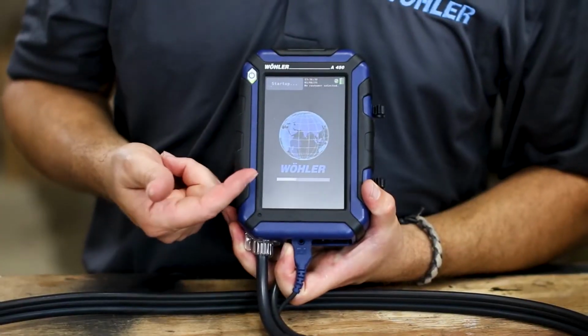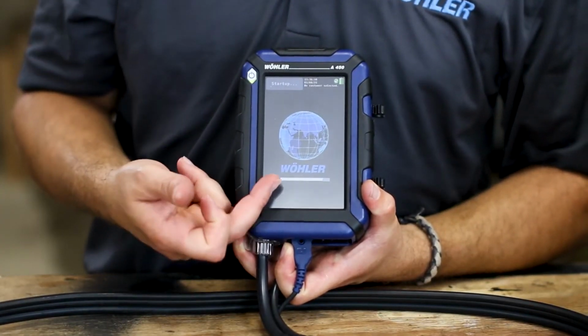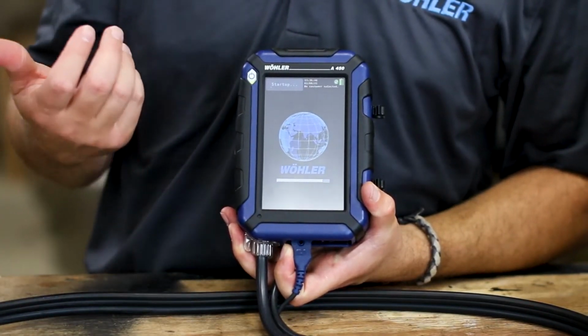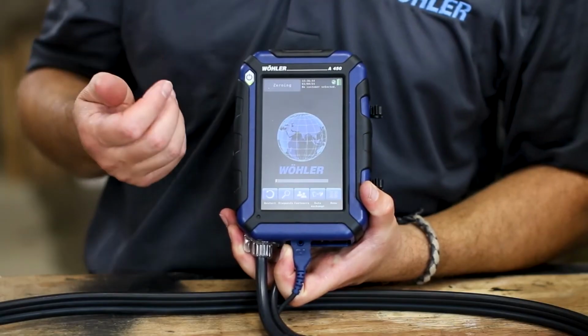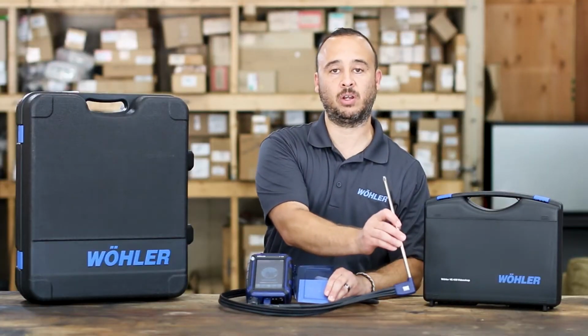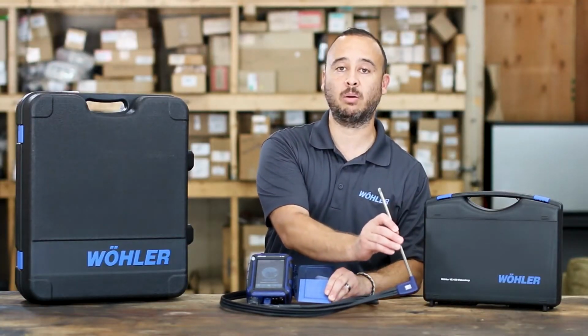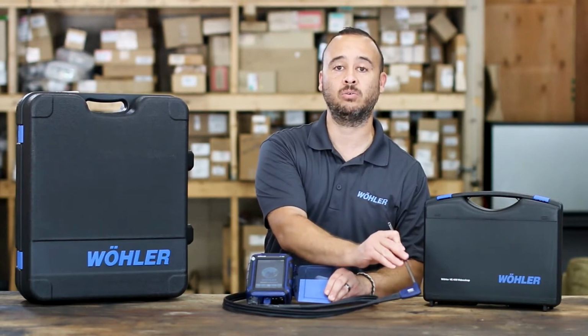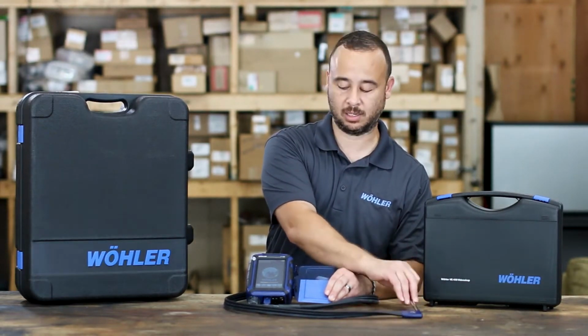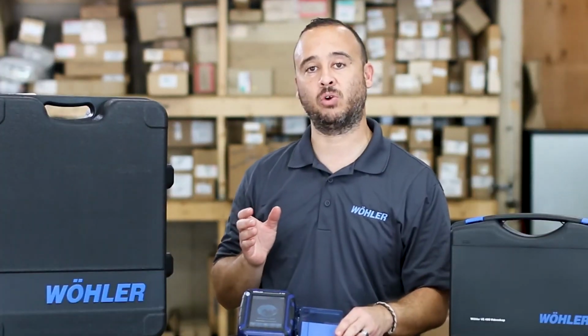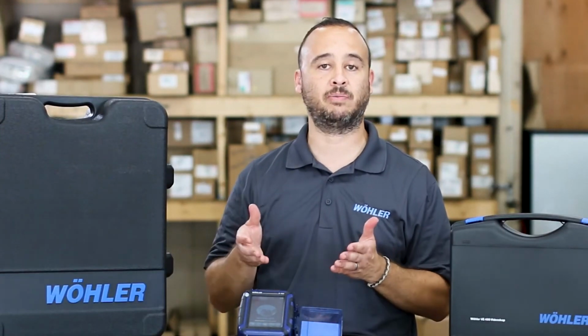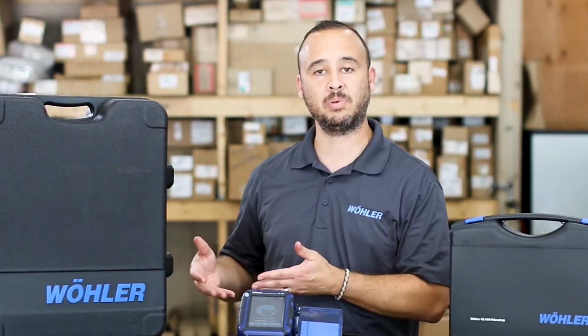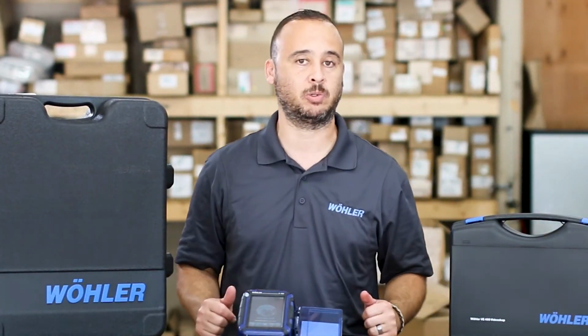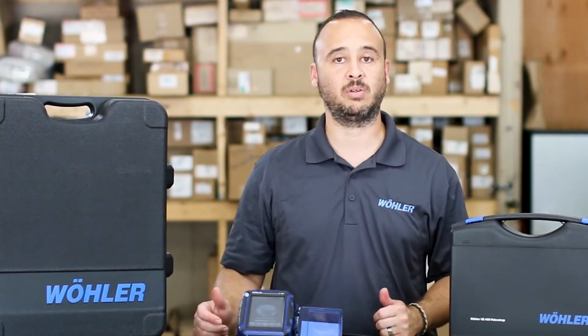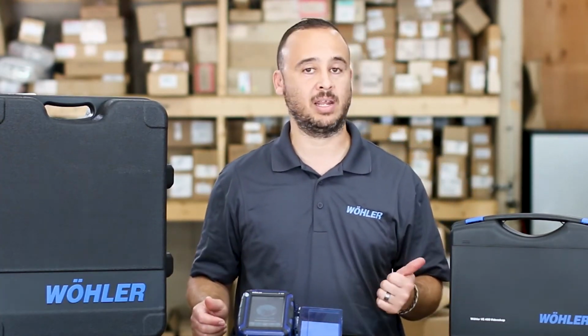Once the power sequence comes on, you'll notice a timing or status bar indicating zero time. While the pump is running, it's measuring the atmosphere it's in, letting it zero and balance itself out so you can start a new service or inspection process. Before doing this, make sure the unit sits at least 10 to 15 minutes in the ambient temperature area where you'll perform your inspection, so it doesn't receive false readings of temperature or gases in the air.